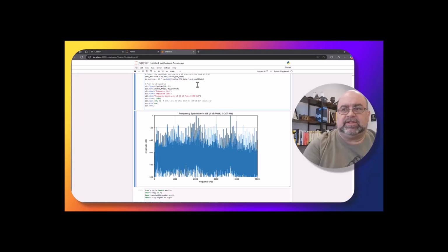Even though the sound, you could hear, was a little different. So let's zoom in, because right now it's showing me a line frequency peak of about 2 kilohertz. That would actually be the firing frequency of the drive. So the sound focused on the sound waves from the drive noise versus the machine itself.